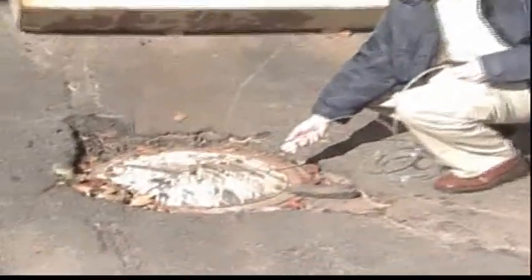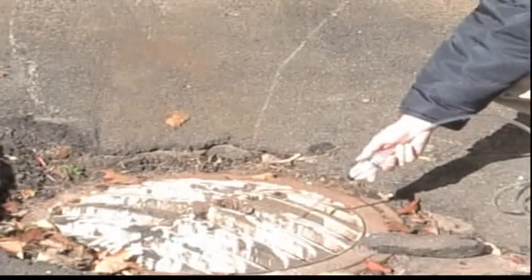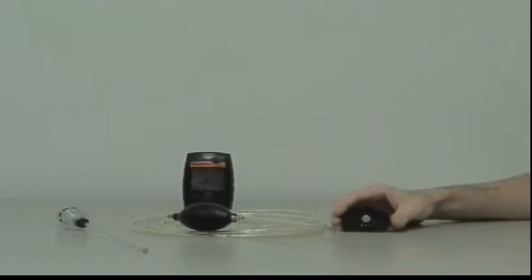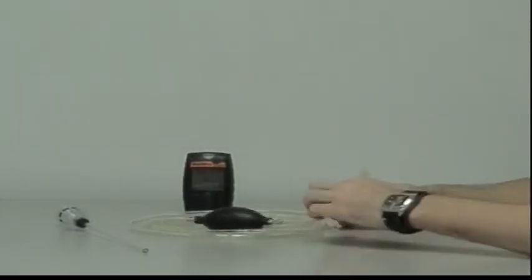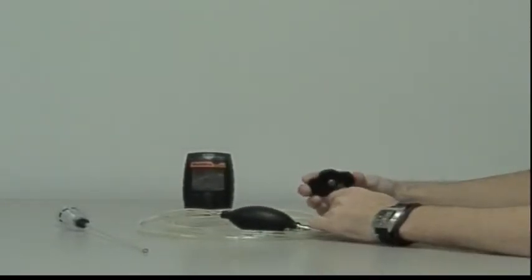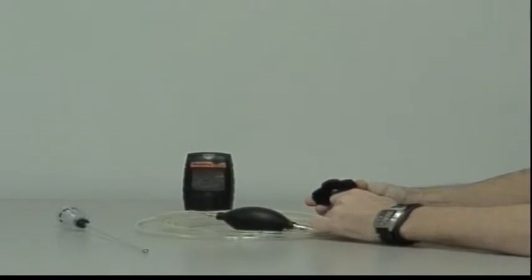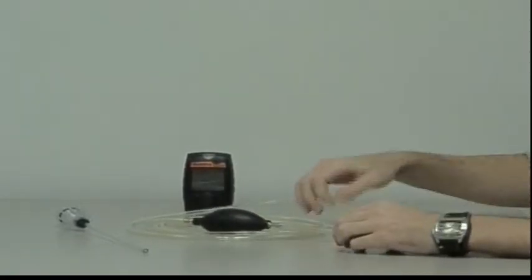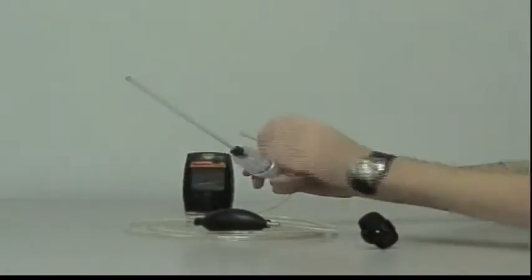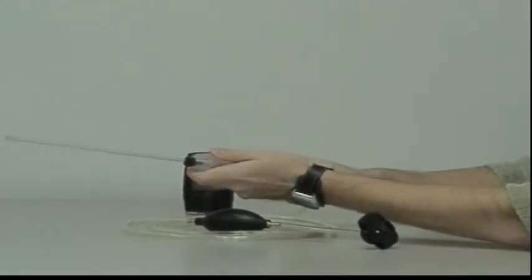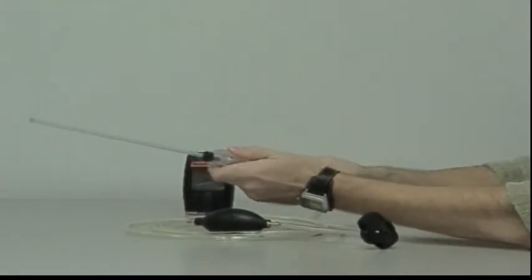The MultiPro can also be used to sample remote locations with the optional hand-aspirated sample draw kit. To use the manual sample draw kit, connect the short section of hose that comes from the squeeze bulb to the sample draw adapter. The hose should be attached to the port at the right and below the knurled screw on the adapter. Then connect the other end of the hose to the sample probe.